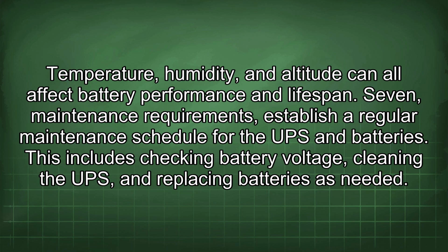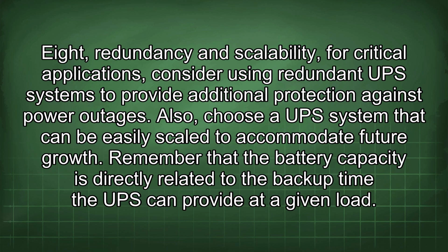Seventh, maintenance requirements. Establish a regular maintenance schedule for the UPS and batteries. This includes checking battery voltage, cleaning the UPS, and replacing batteries as needed. Eighth, redundancy and scalability. For critical applications, consider using redundant UPS systems to provide additional protection against power outages. Also, choose a UPS system that can be easily scaled to accommodate future growth. Remember that the battery capacity is directly related to the backup time the UPS can provide at a given load.